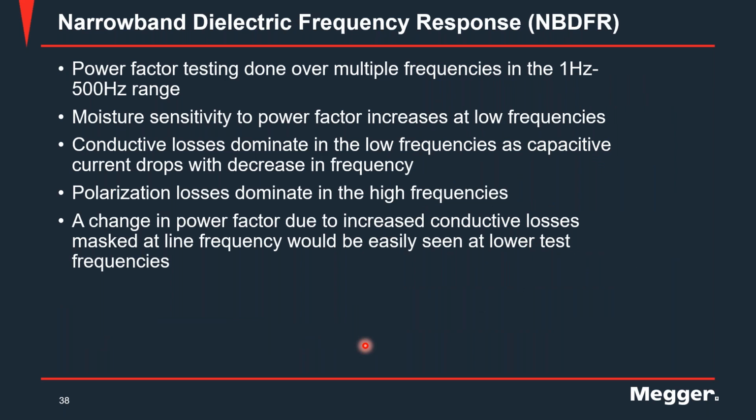So the variable frequency power factor testing exploits these concepts, and it uses these concepts to determine the state of the insulation. It gives us information where we can detect changes happening in the insulation before a traditional power factor test can.